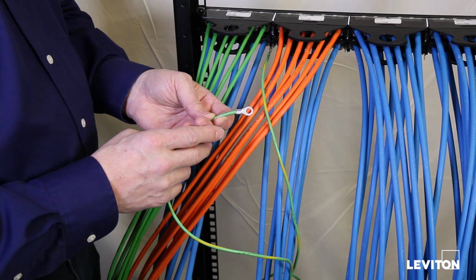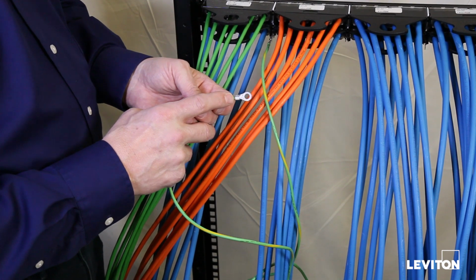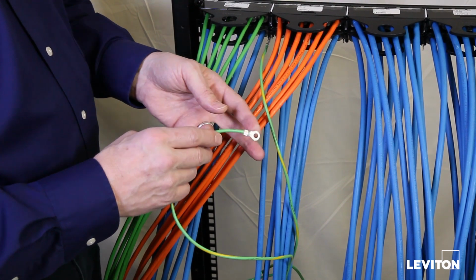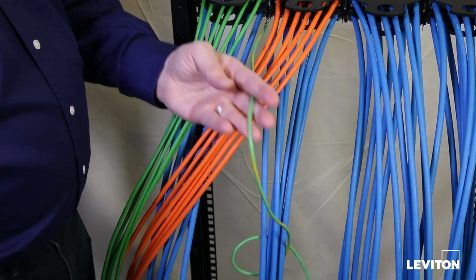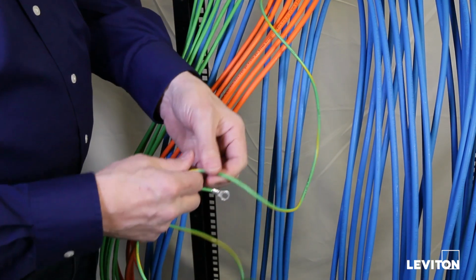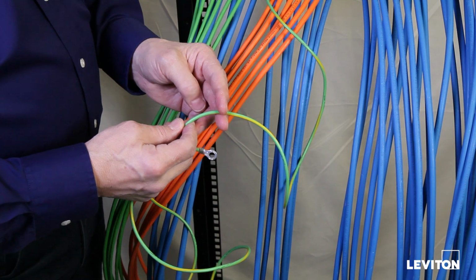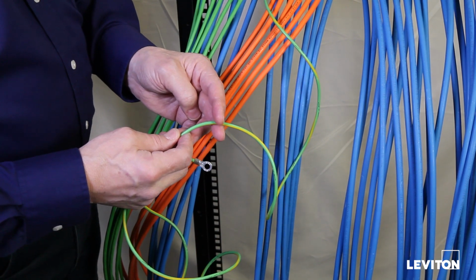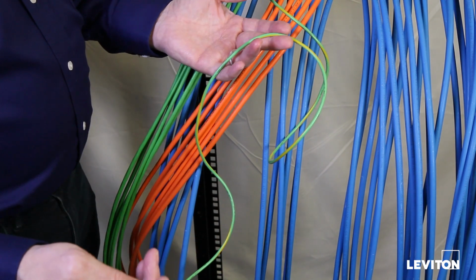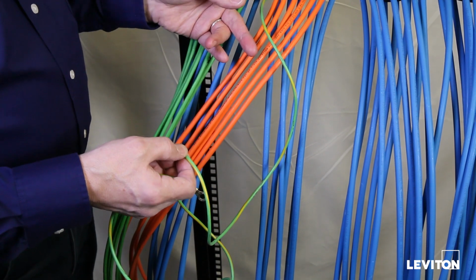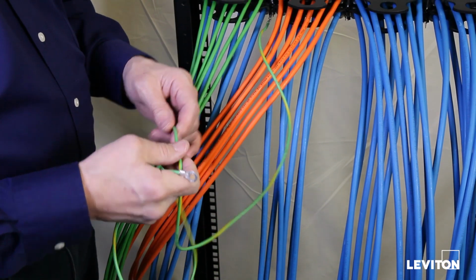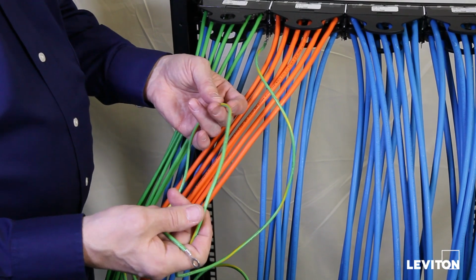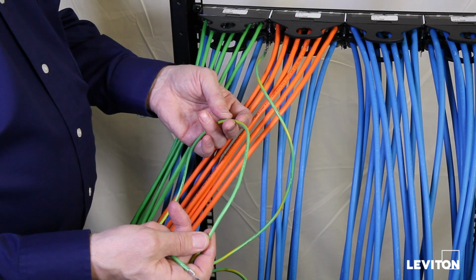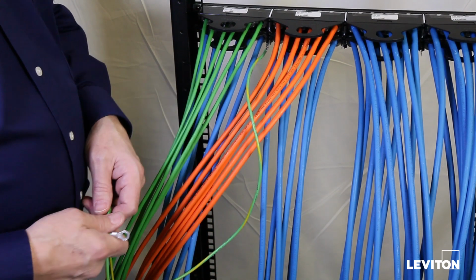Once your angled or flat panel is fully loaded, extend your earthing jumper. Attach the ring terminal to the rack bonding bus bar. If the jumper is too long, you can cut it shorter and supply your own ring terminal. If it's too short, you can easily create your own earthing jumper with an M6 ring terminal, a 6mm spade lug, and a 4mm square ground wire of the correct length.